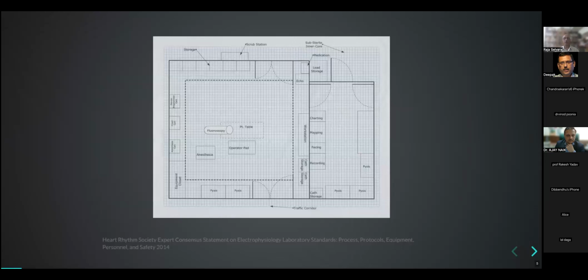So to start off with the setup, some points on how to set up the lab. If you're setting up a lab fresh, or looking at revising your setup, one good thing to do, which we have also not done, is to have the console outside the primary EP room. This helps with reducing fluoro exposure. Only the operators stay inside the room, and the others can stay outside. You don't need to wear lead shields, and that is ergonomically very beneficial. Overall, this is a better way to operate.